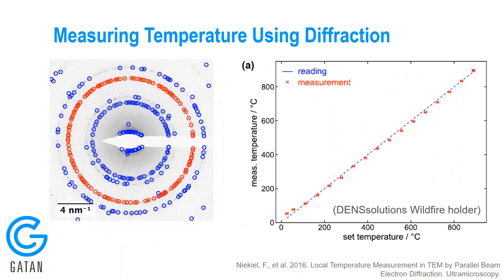Here's another example from a group in Germany. In this case, they used electron diffraction to measure the temperature by measuring subtle shifts in the lattice spacings of the material. As the sample is heated, the lattice expands, and they can do very precise measurements of these diffraction rings. They did very careful calibration and additional alignments of the microscope optics to really do careful measurements of the lattice spacings as they're heating the sample.